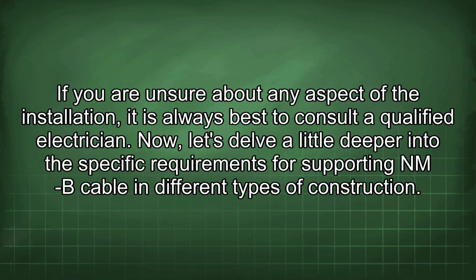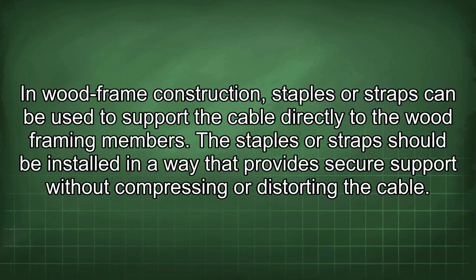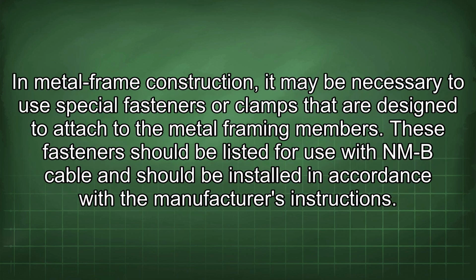electrician. Now let's delve a little deeper into the specific requirements for supporting NMB cable in different types of construction. In wood frame construction, staples or straps can be used to support the cable directly to the wood framing members. The staples or straps should be installed in a way that provides secure support without compressing or distorting the cable. In metal frame construction, it may be necessary to use special fasteners or clamps that are designed to attach to the metal framing members.